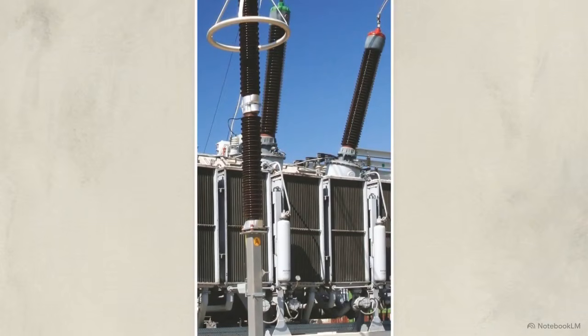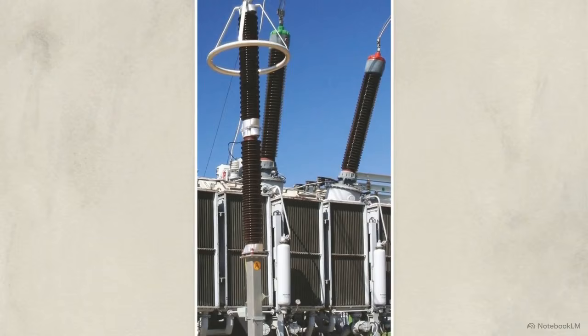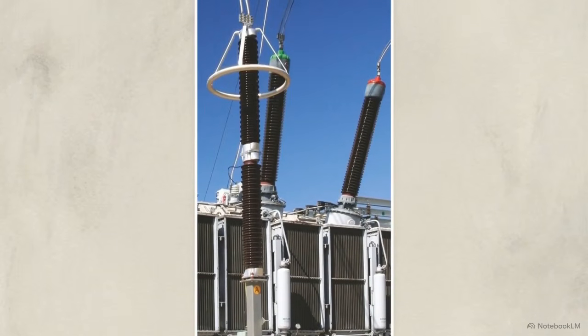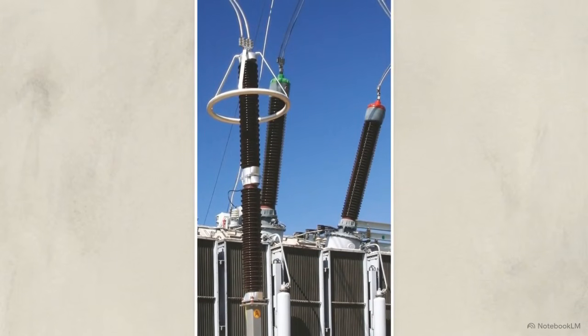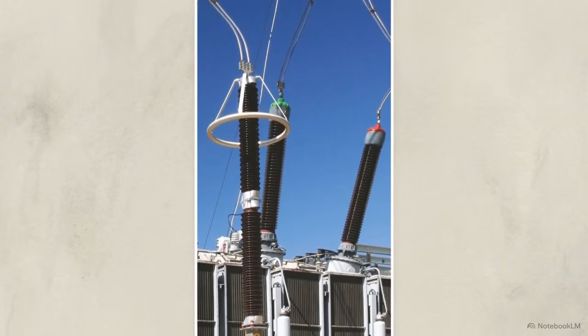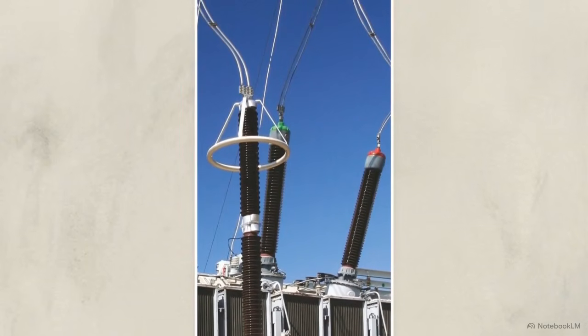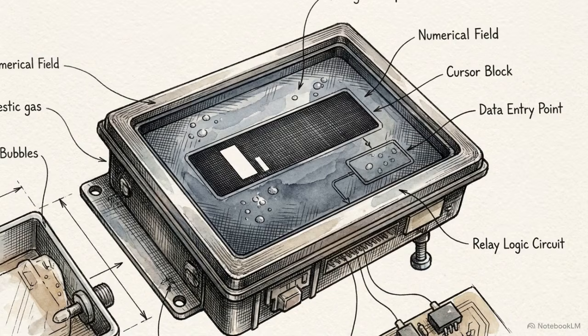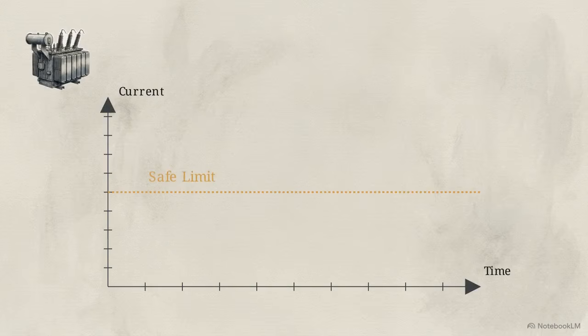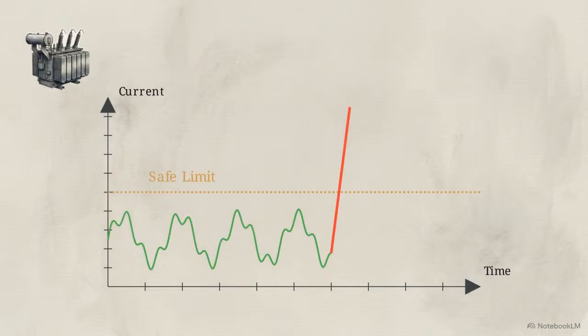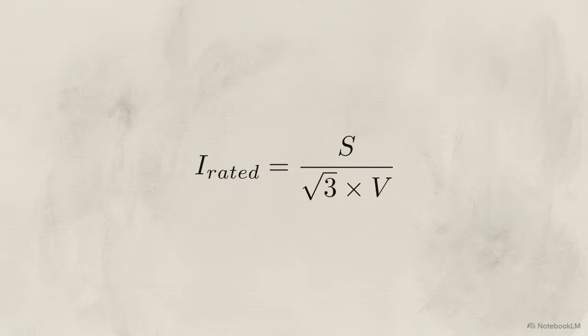To guard against a severe external short circuit, engineers utilize IDMT overcurrent protection. This relies on current transformers mounted directly on these high-voltage bushings. The engineering challenge here is calculating the exact primary pickup current. This threshold must be high enough to allow normal operational surges, but low enough to trip the circuit the moment a real fault occurs. The calculation starts by finding the full load current.